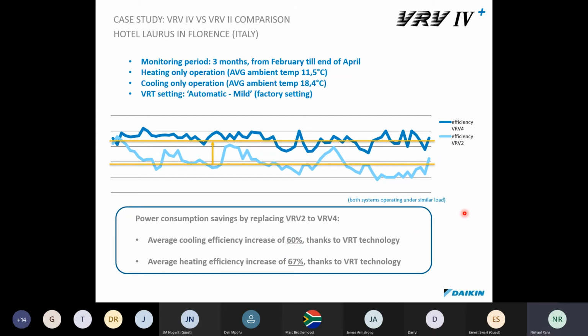So obviously the efficiencies weren't there. So you look at an average of a minimum of 60% better efficiency from your older VRV to your newer VRV. So you could even get a call from your customer saying, hey, I've got this old VRV system, it works like a bomb, but yes, the energy bill's crazy on this thing. You can tell him, no problem, Mr. End User. We've got a solution for you. The VRV condensers are backward compatible. The condensers use more than 80 to 90% of the total system's energy. If we change this, we can achieve an estimate of about 60% reduction in your electrical consumption.